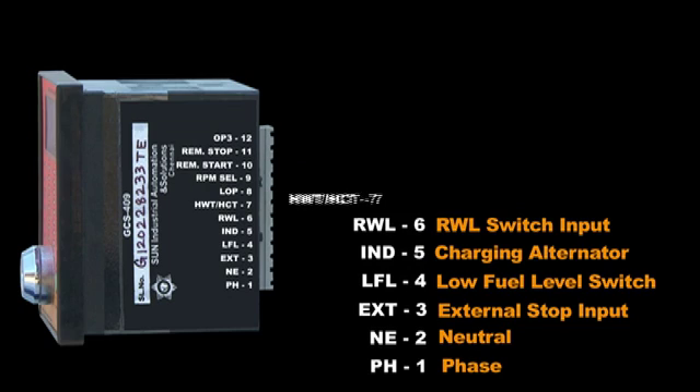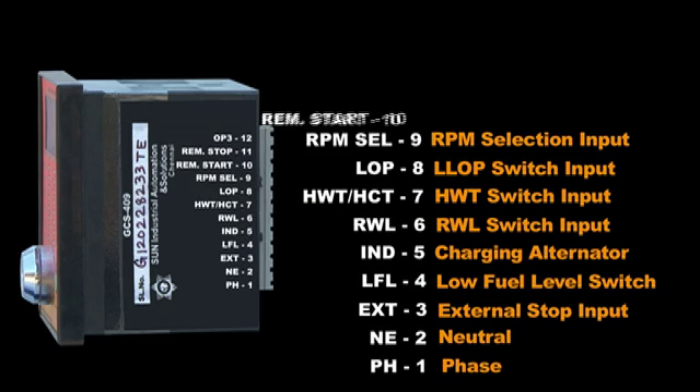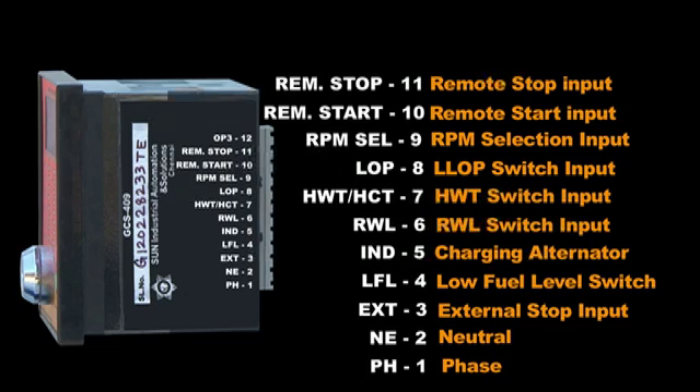Terminal 7: high water temperature switch input. Terminal 8: low oil pressure switch input. Terminal 9: RPM selection input. Terminal 10: remote start input. Terminal 11: remote stop input. Terminals 10 and 11 are connected to the PLC for start and stop commands.